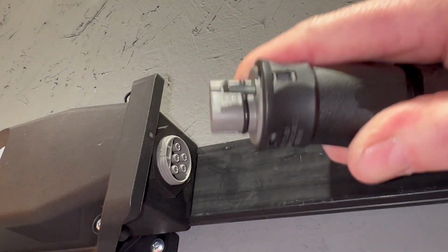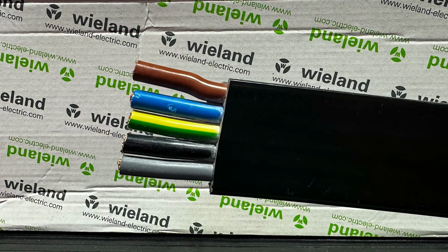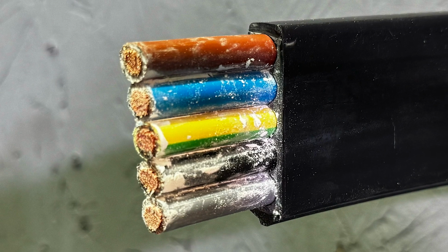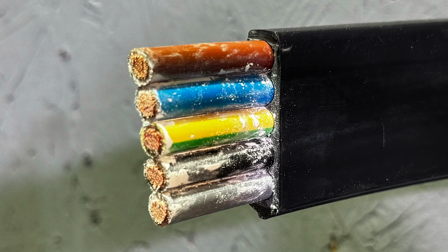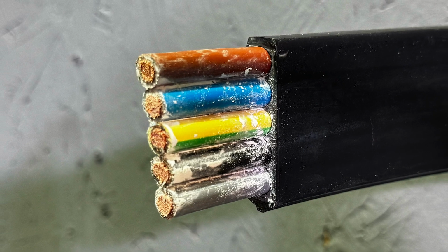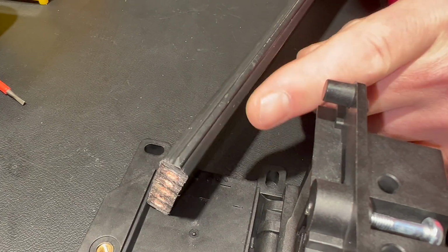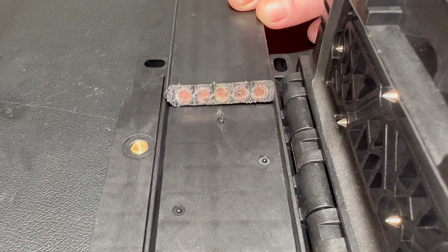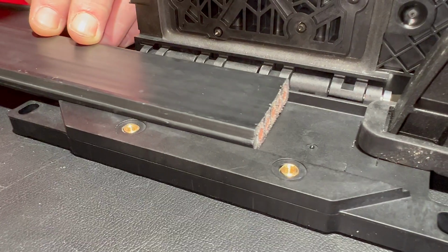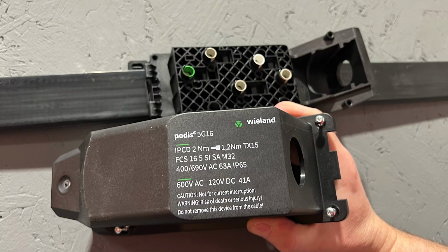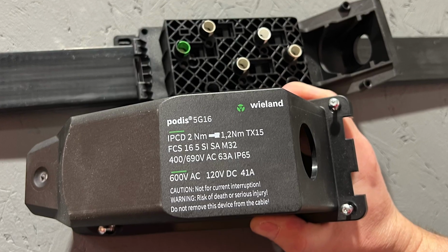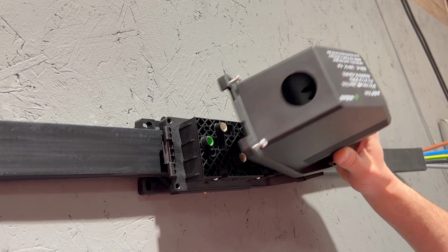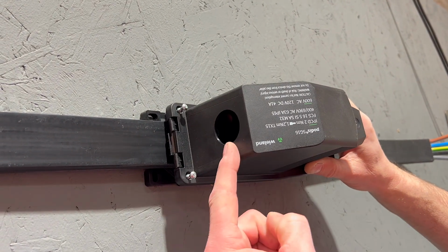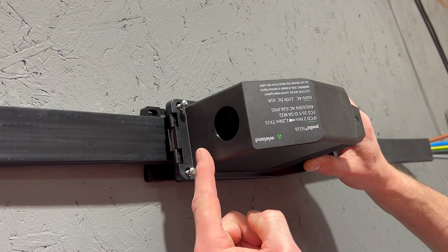The ability to disconnect locally also helps with the initial and periodic electrical testing. The busbar system, rated at 63 amps, uses 16mm squared conductors arranged in a 3-phase neutral and earth configuration. Its cleverly designed cable is keyed to prevent incorrect installation of the boxes. The system is versatile, allowing for power through connection modules that resemble tap-off boxes. These modules can be positioned along the cable, facilitating the connection of a 16mm squared supply cable.